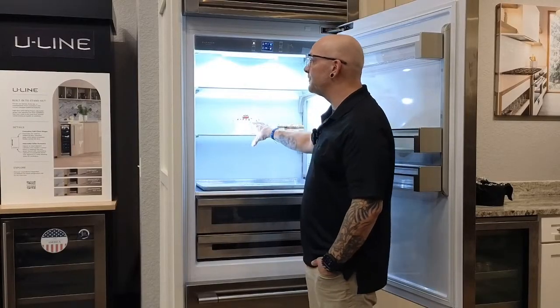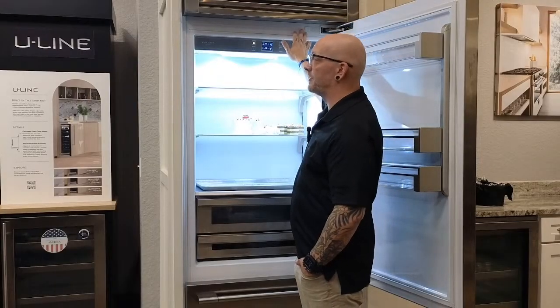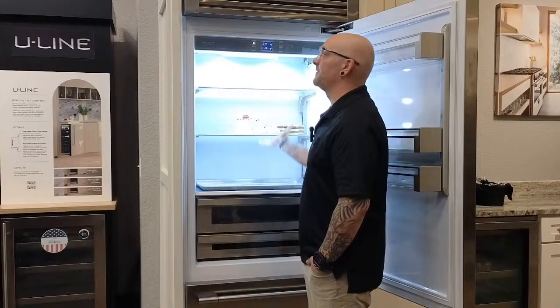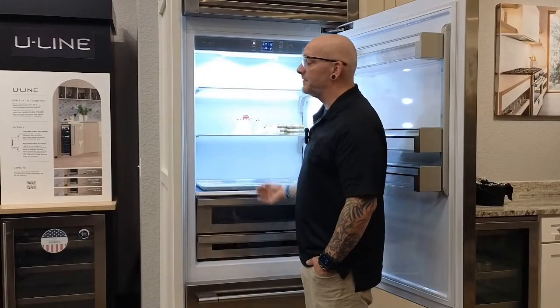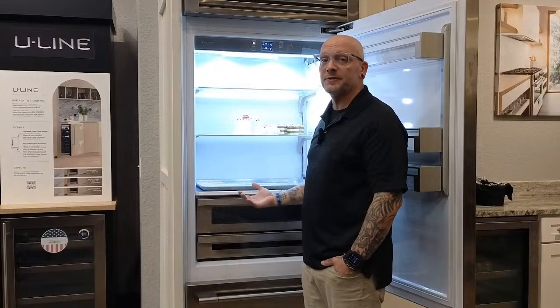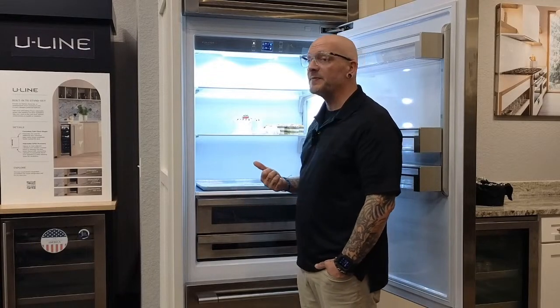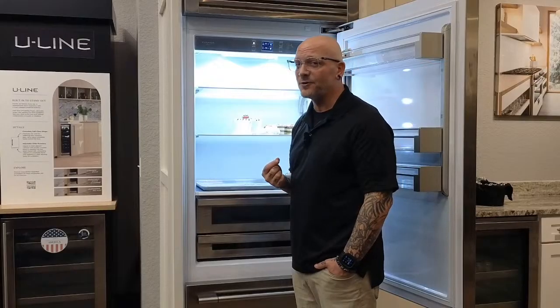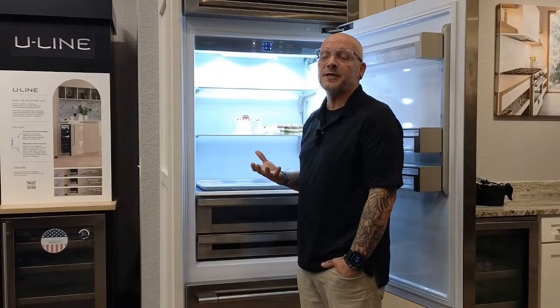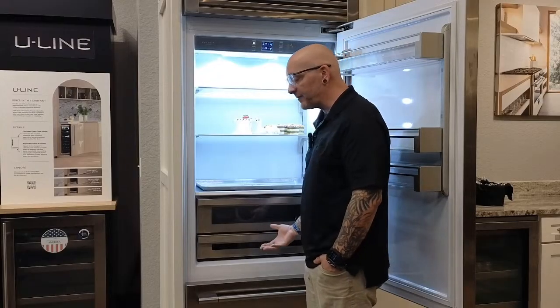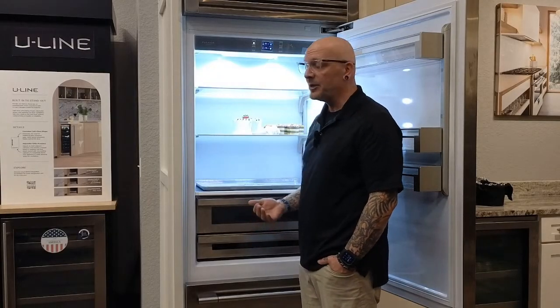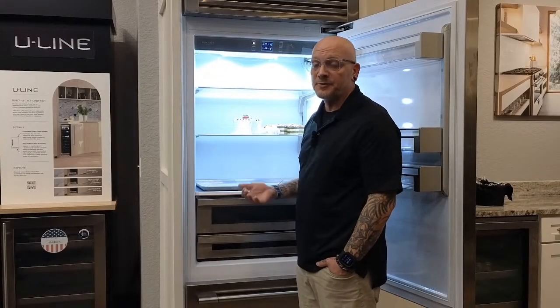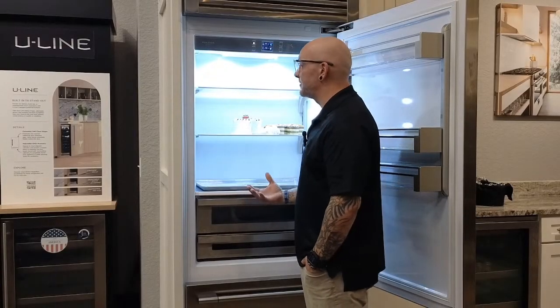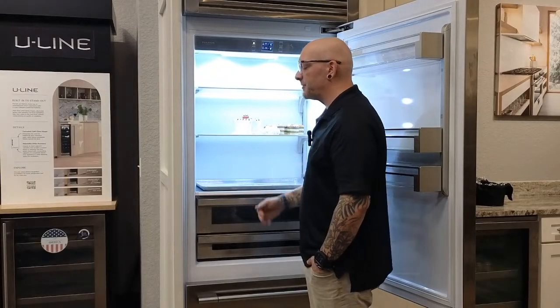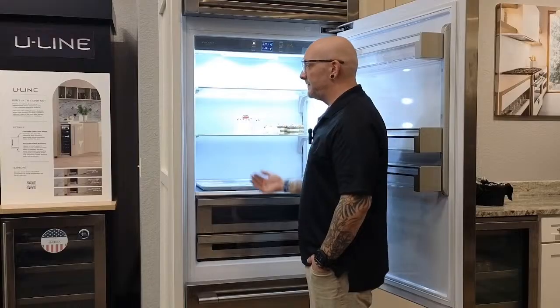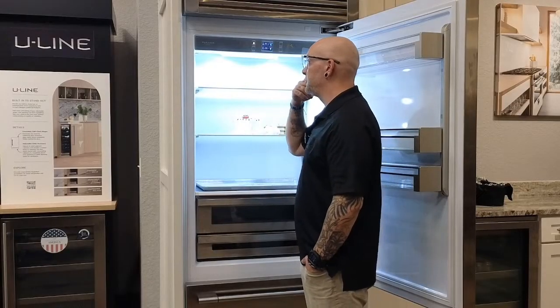So if we're having some fresh food issues, let's say the fans aren't coming on, the lights aren't going off because the reed switch is bad, and then our temperatures in the fresh food section are up in the high 40s, the freezer is going to start to be affected, and probably the first thing they're going to notice is no ice, because the ice maker sensor needs to be at 14 degrees to actually start to harvest, or even think about harvesting ice. So they could have a nice deep freeze, frozen ice cream, everything looks great inside, but it may only be 18 degrees. So 14 degrees is where the ice maker is going to want to harvest. So as fresh food temperature starts to rise, the freezer can be affected too. Just be mindful, they do share a condenser. That's the only thing they do share.